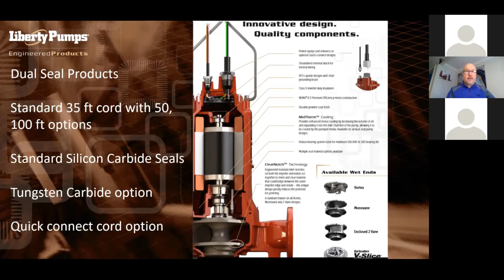So here we're talking about some of the differences of features that we have in the dual seal product. I mentioned the quick connect cord option, terminal block for internal wiring, VFD capable design, meaning that it comes standard. These pumps come standard with the shaft grounding brush for VFD type applications, as well as Class H inverter duty insulation, which is a higher grade insulation than most manufacturers use. You'll see a lot of Class F insulation out there. We chose to just upgrade to the Class H insulation to make it inverter duty, also able to handle higher temperatures and just a superior insulation design.